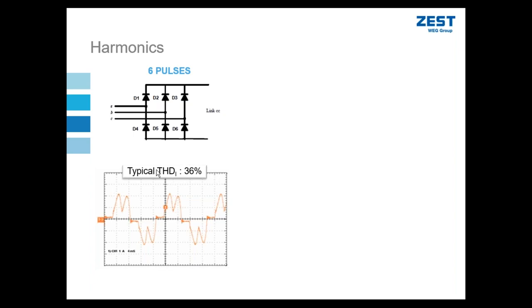So for example, in this case, I'm showing that the THDI of a six pulse rectifier at full load is 36%. The amplitude of the distorted current could be, let's say, for example, 50 amps. At reduced load, if I put low load on the motor that this VSD is driving, my THDI percentage will increase to as much as, let's say, for example, 60%. However, because I'm at a low load condition, my absolute amplitude of distorted current would be less than the previous example, and it could be as low as, say, 20 amps. So even though my THDI as a percentage is higher under that lower load condition, the actual effect that it has to distort my voltage is less. Just something to take into consideration.